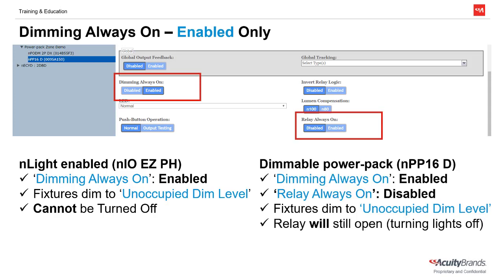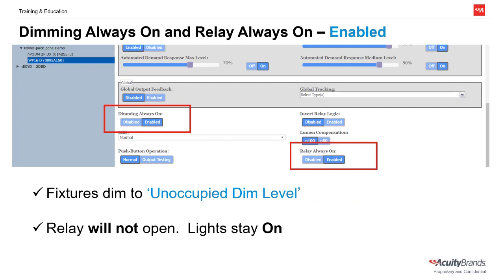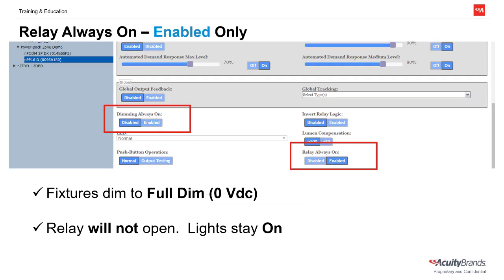If we're programming a dimmable power pack, enabling Dimming Always On only will not necessarily keep the lights on. If we keep the setting Relay Always On disabled, even though the dimming will be instructed to dim to the unoccupied dim level, the relay will still open, turning off anything connected to it. If we wish for the lights to remain on, we will need to enable Relay Always On. With both of these settings enabled, the lights will remain on at the unoccupied dim level. If we only have Relay Always On enabled and do not enable Dimming Always On, the lights will dim to full dim or 0 volts DC, regardless of the unoccupied dim level. Note that this light level will vary depending on the make and model of the fixture wired to the dimmable power pack or relay.